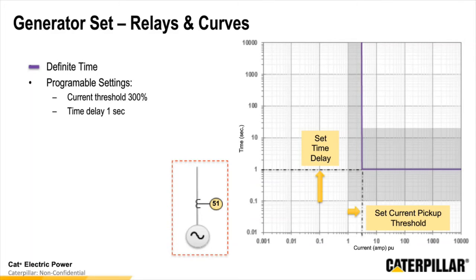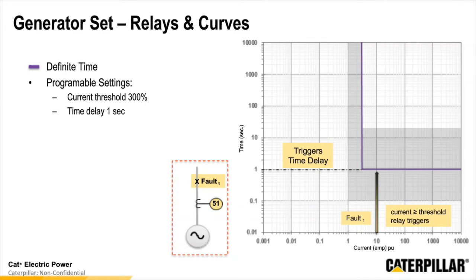So now, if we were to have a fault within the system, that would be something greater than 300%. So in this case, we're showing 10 times the rated current. Again, with most generators, you're going to need to work with your manufacturer to understand if 10 times the rated current is available from your generator. That's going to depend on the current decrement curve that you're able to get from your manufacturer. That will also depend on whether or not you're using a permanent magnet excitation system or a self-excited, or whether or not you've got enough subtransient reactance within the generator to actually provide a large amount of current. So those numbers will determine whether or not you can get to 10 times, but for this example, we're going to say that we can. And then at 1 second, the generator would trip offline, and that would be our trigger.